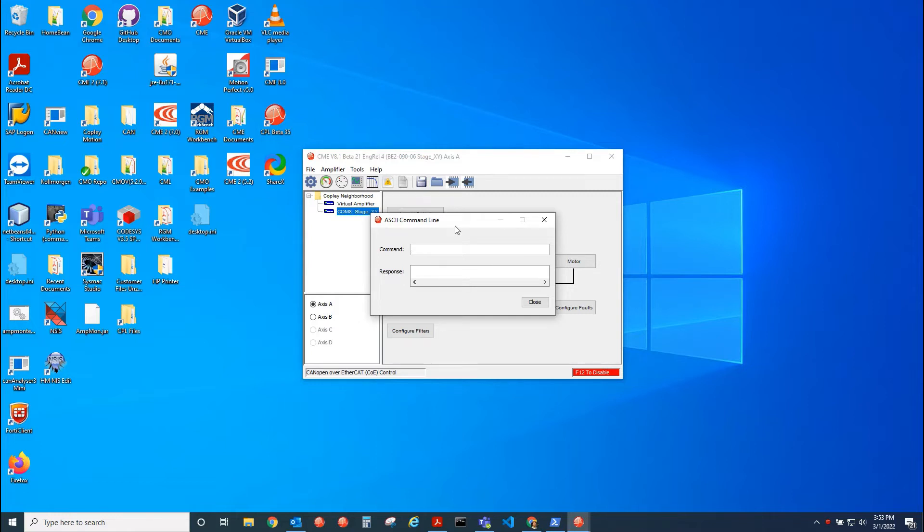So I say get r0x121. Right now it's zero. That means it's in EtherCAT mode. If I had Ethernet firmware in this drive, bit nine would be set in this parameter, meaning it would be hex 200.